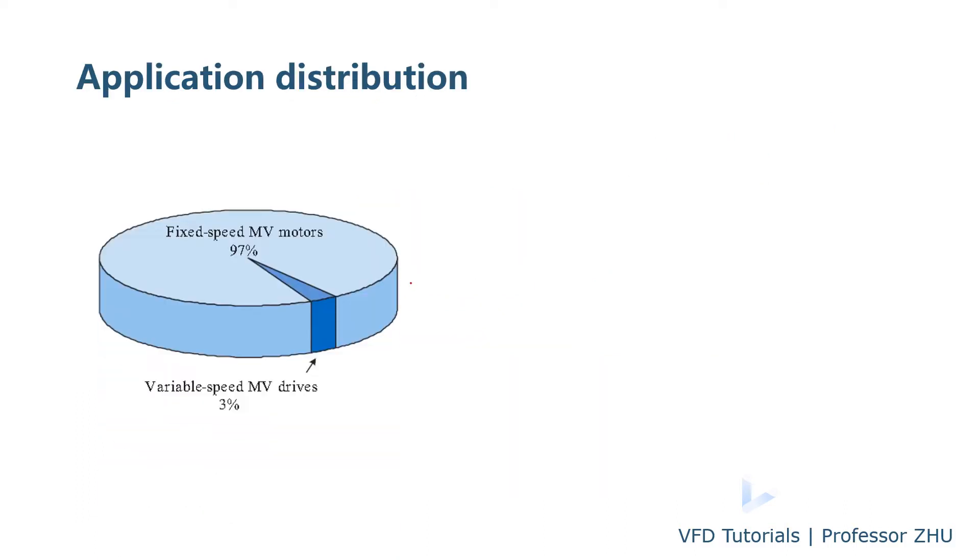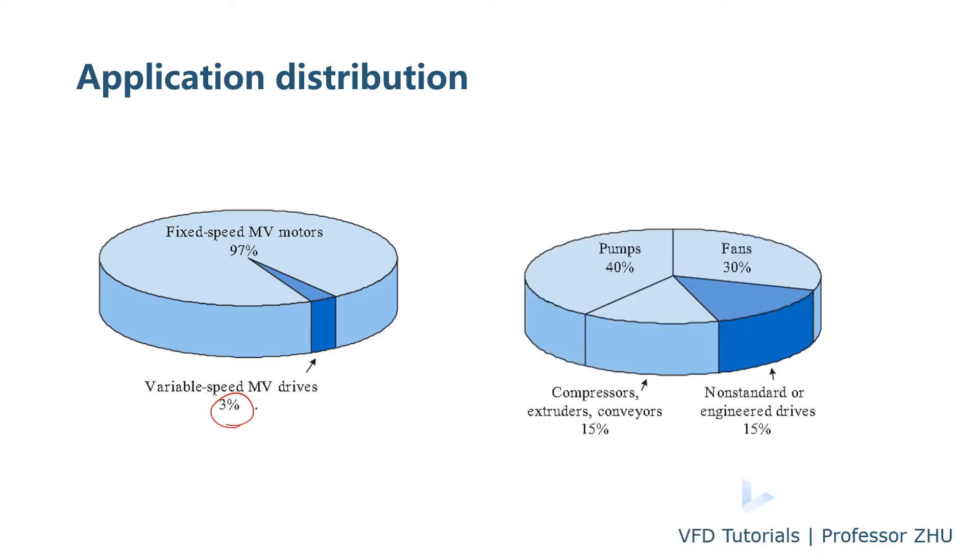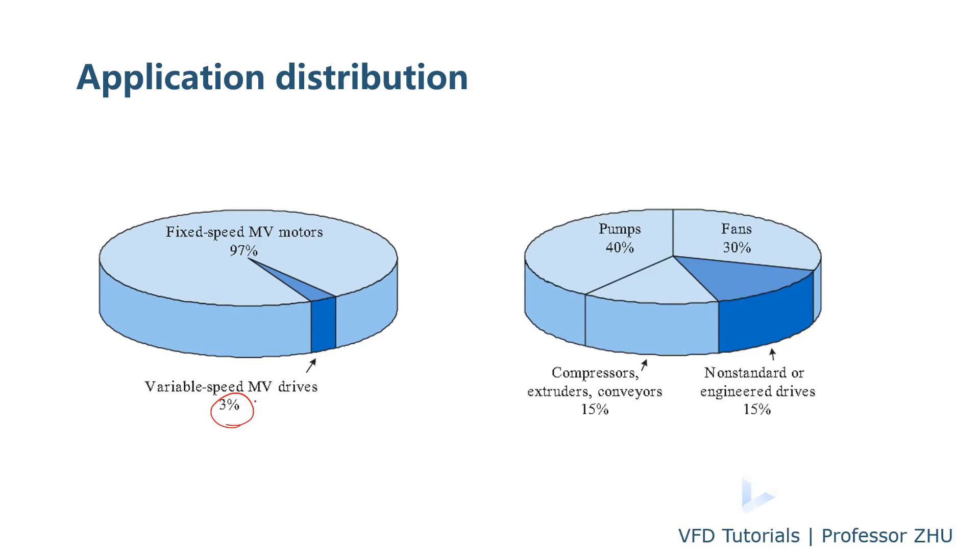For the medium voltage motor, the majority is fixed speed. Only about 3% is driven by the variable speed drive. And for those driven by the VFD, majority of the load type is pump, fan, and compressor. And a very few, a small portion, the load is what we call the non-standard or engineered drive like a roller mill for the steel industry or some test bench.